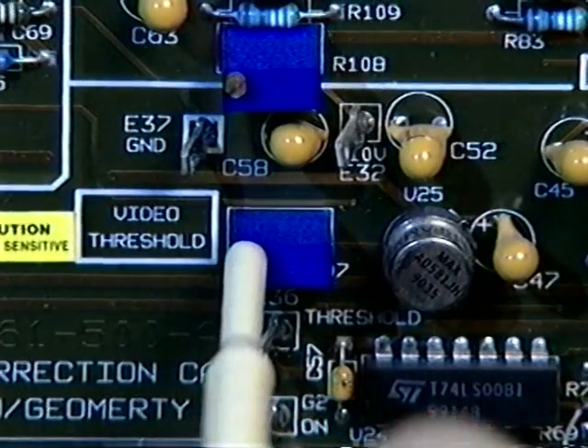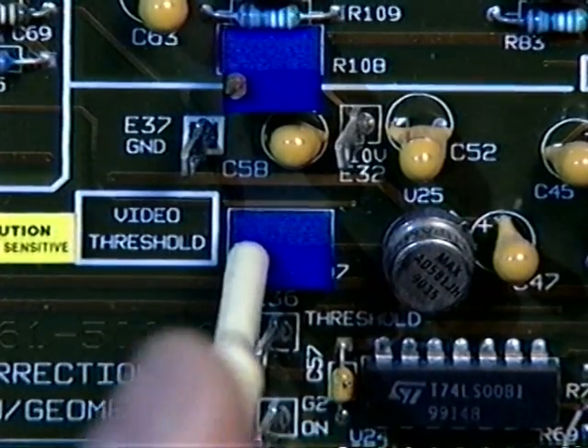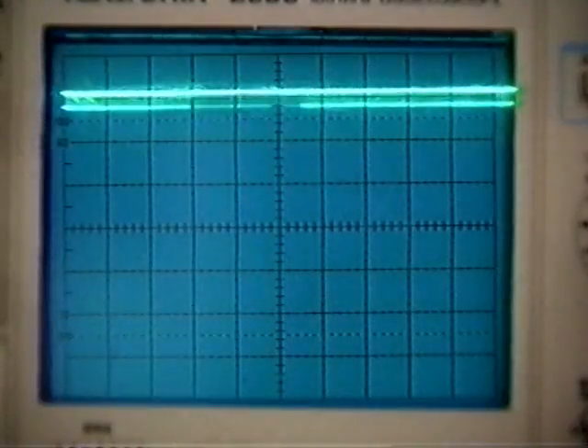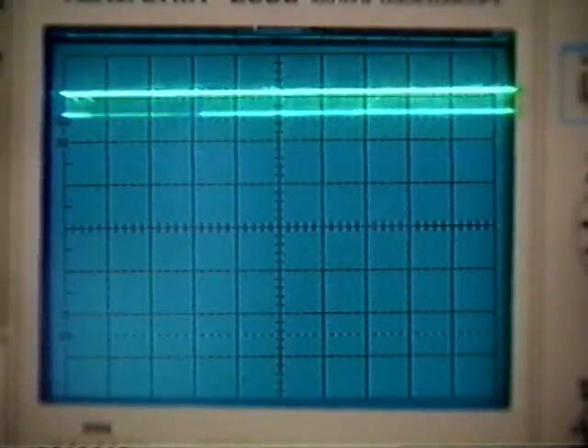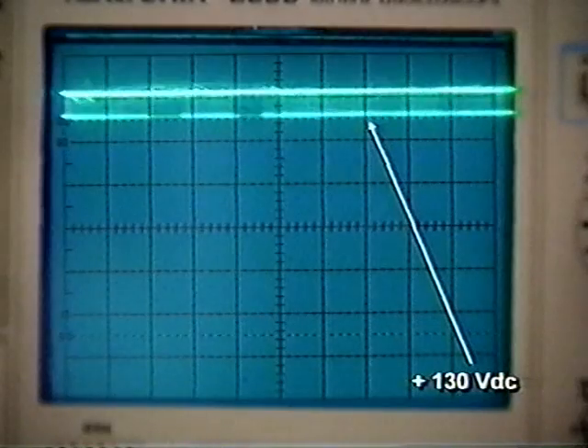Adjust threshold for plus 130 volts DC. Turn the threshold control clockwise so that the line splits into 2 lines. The bottom line should read plus 130 volts DC. The top line should still read about plus 140 volts DC. Verify that there is no light coming from the projector's lens.